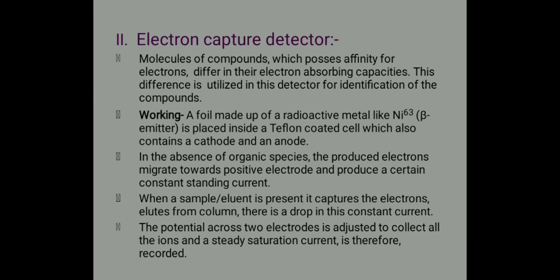Next we have electron capture detectors. Molecules of compounds which possess affinity for electrons differ in their electron absorbing capacity. This difference is utilized in this detector for identification of compounds.